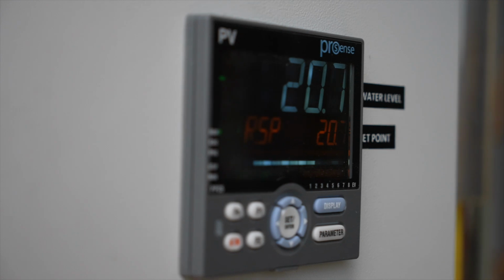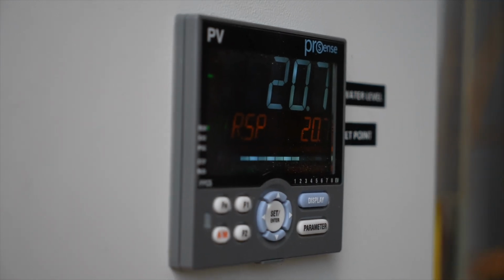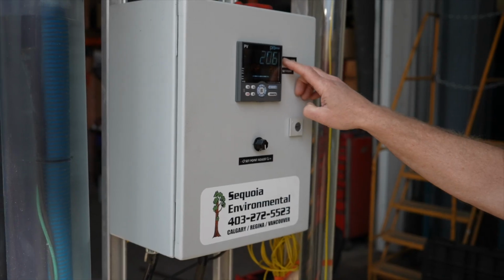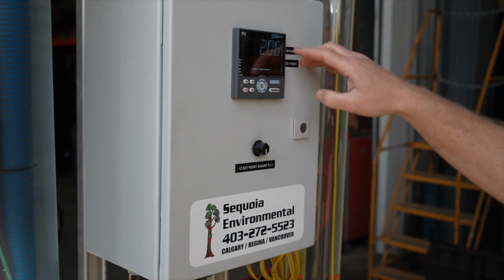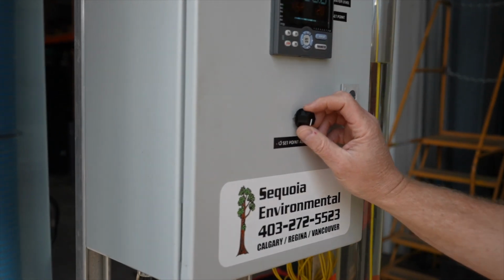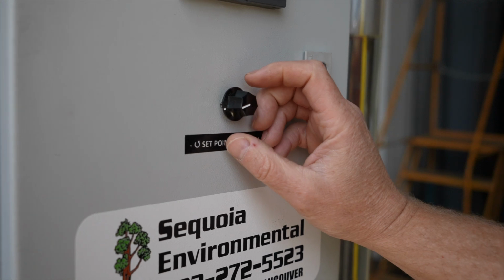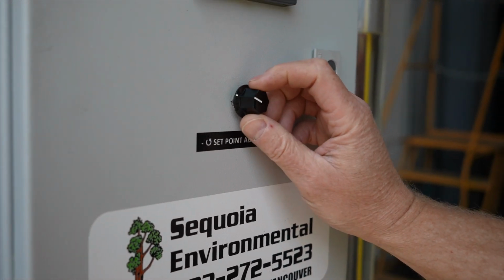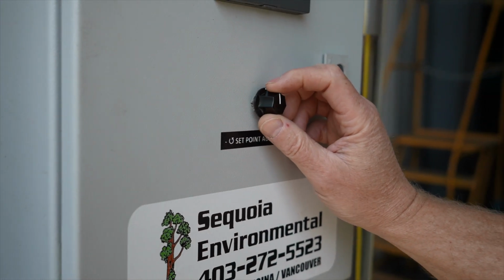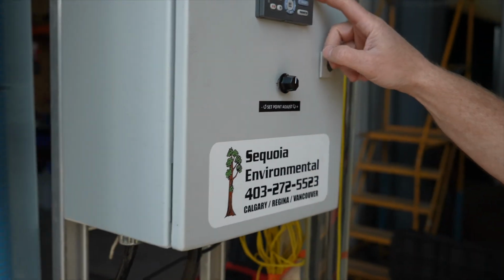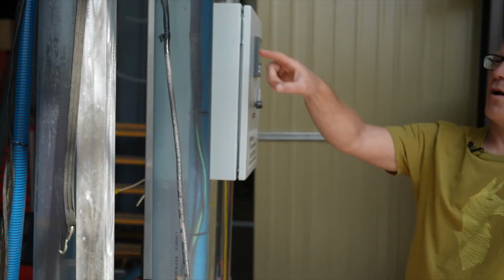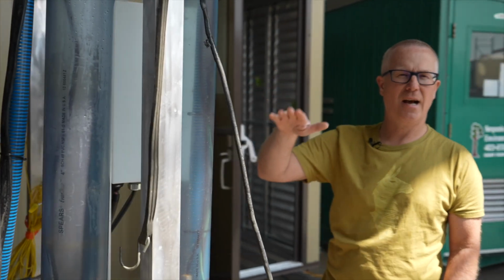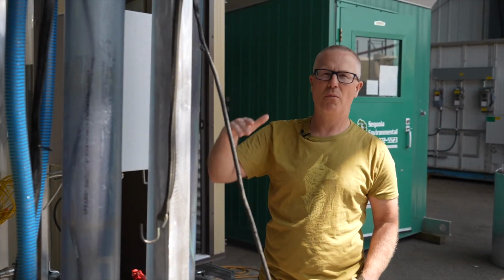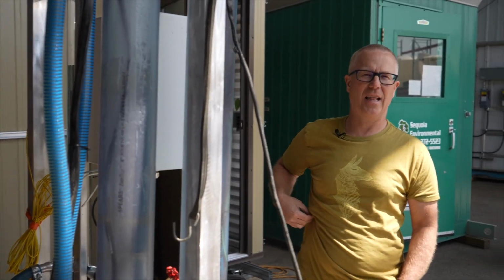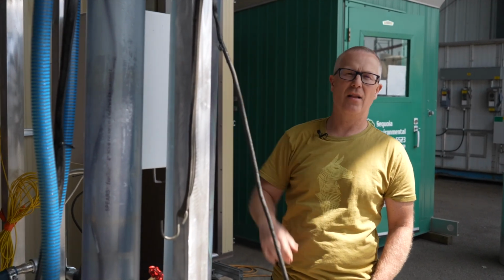If you get a view of the screen, you can see we currently are set up in orange at 20.7. The PID loop is trying to maintain 20.7 above the transducer. Currently it's at 20.6. But if I wanted to quickly increase the pump speed, what I'm doing is increasing the elevation of the water. I've set it now to 23.1. The water level is slowly going up, and it's going to take about a minute or so. Then it actually sustains that level once it hones in on that elevation.